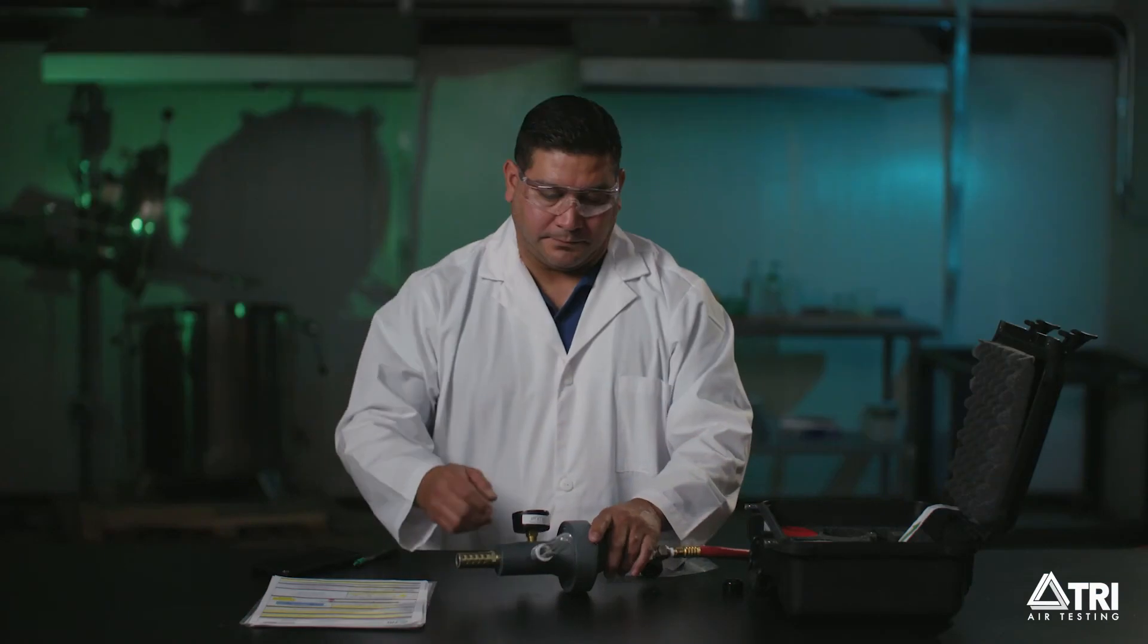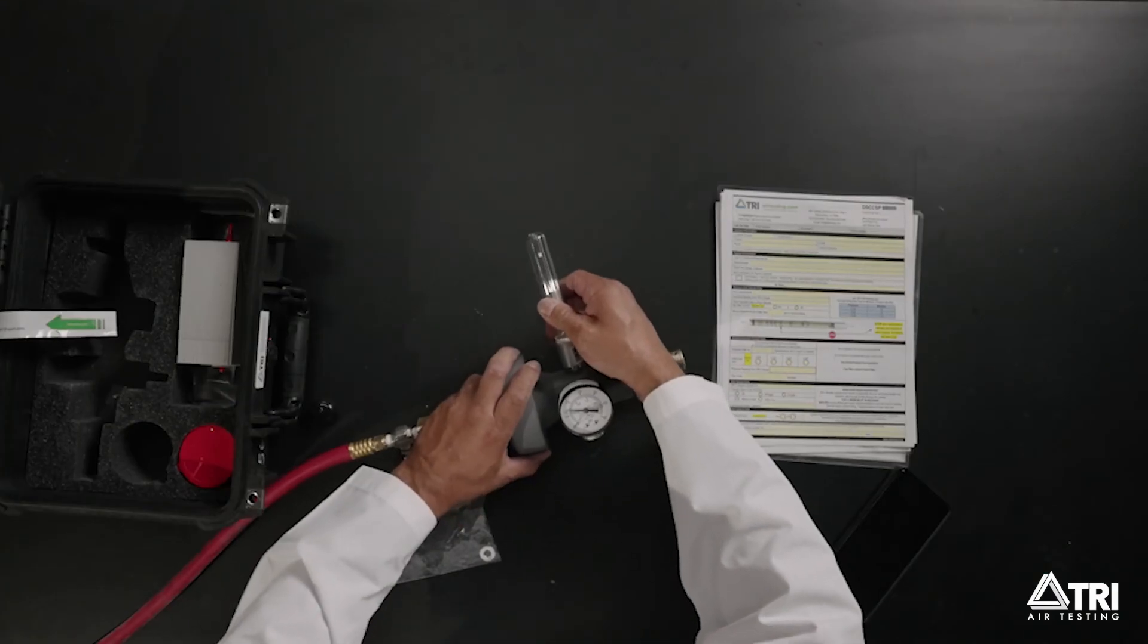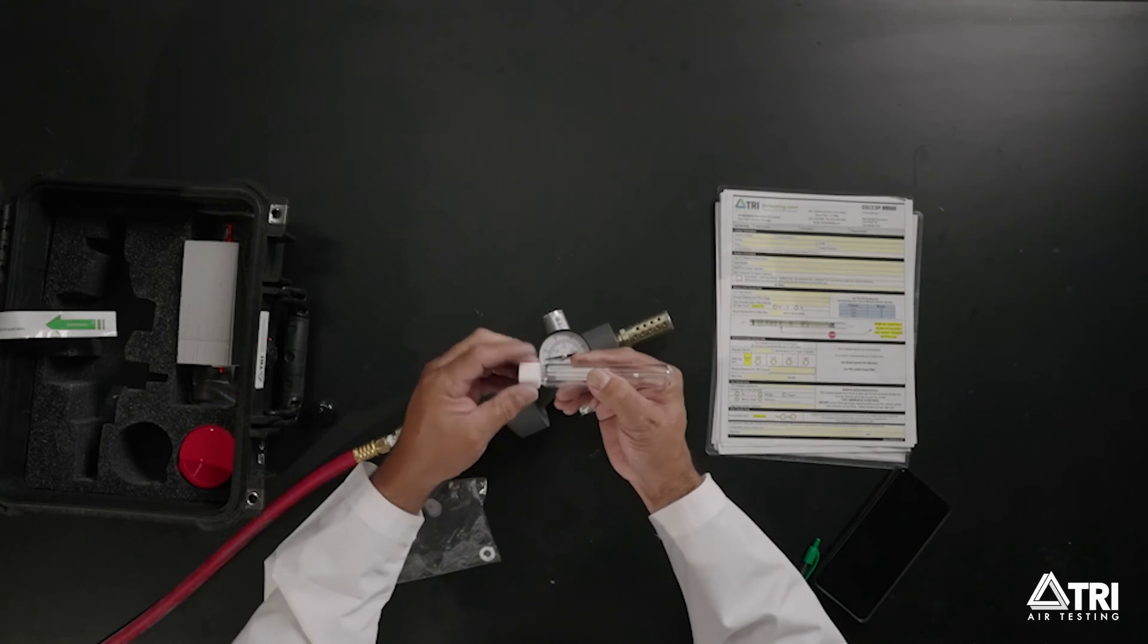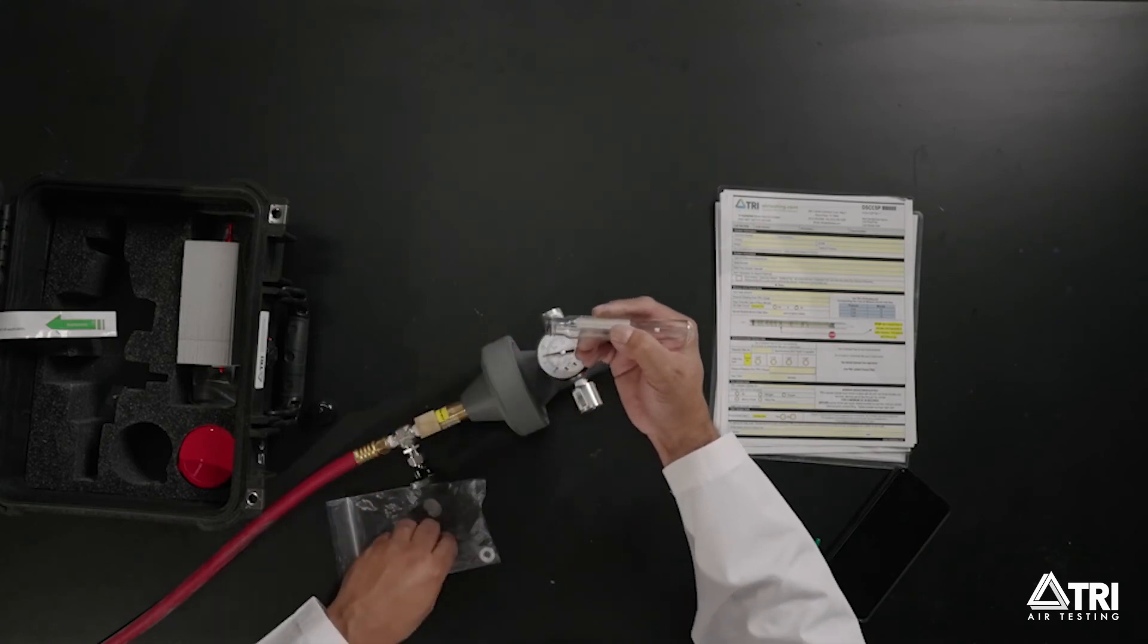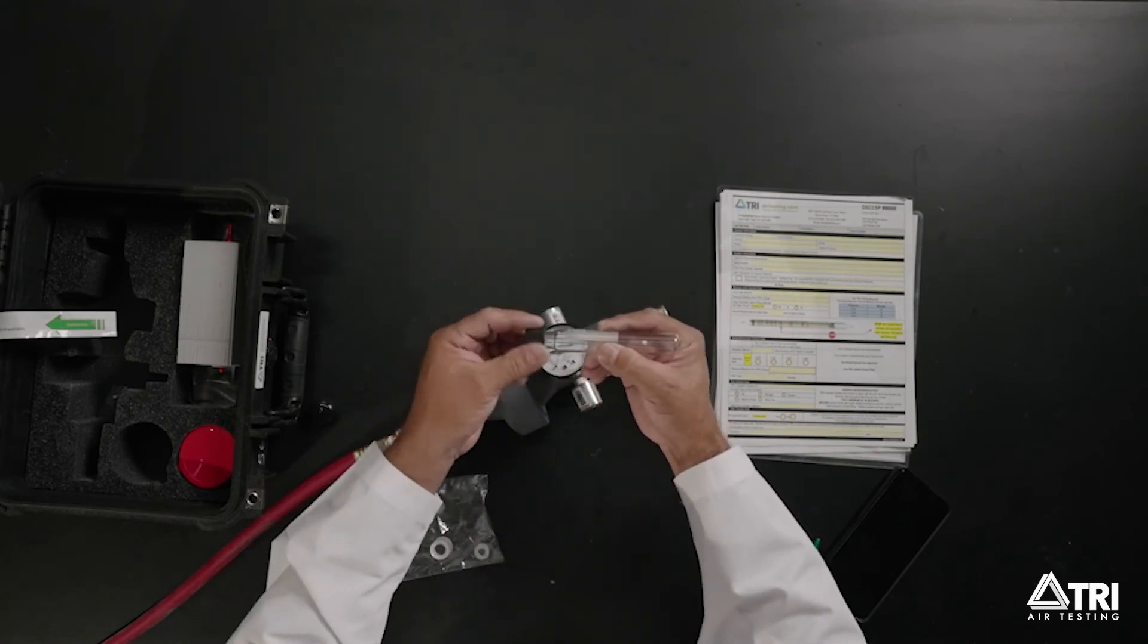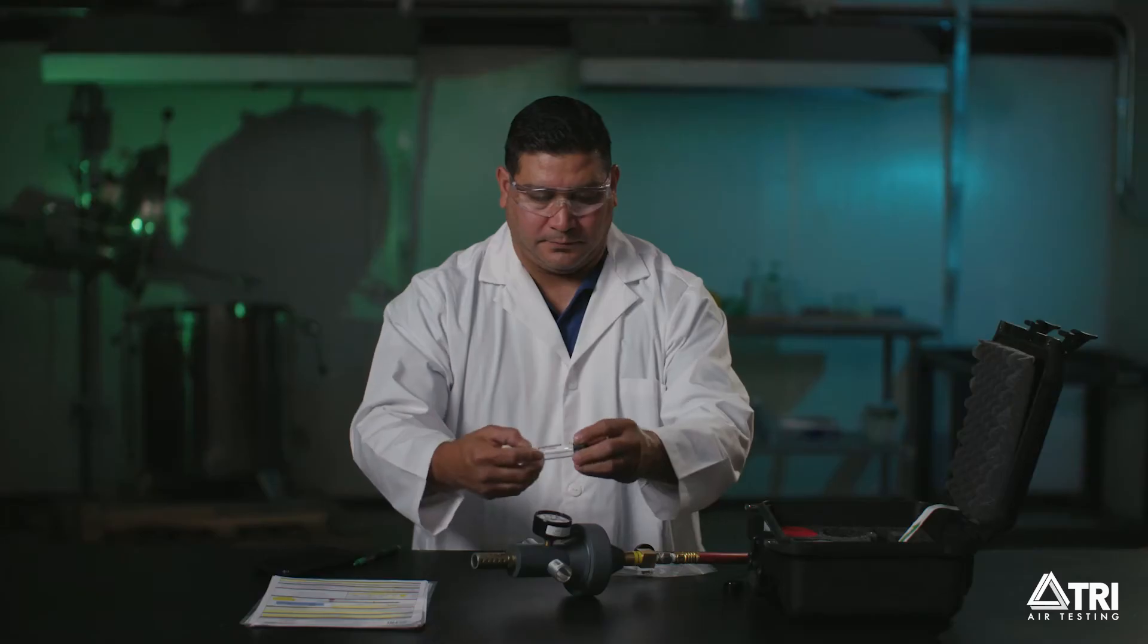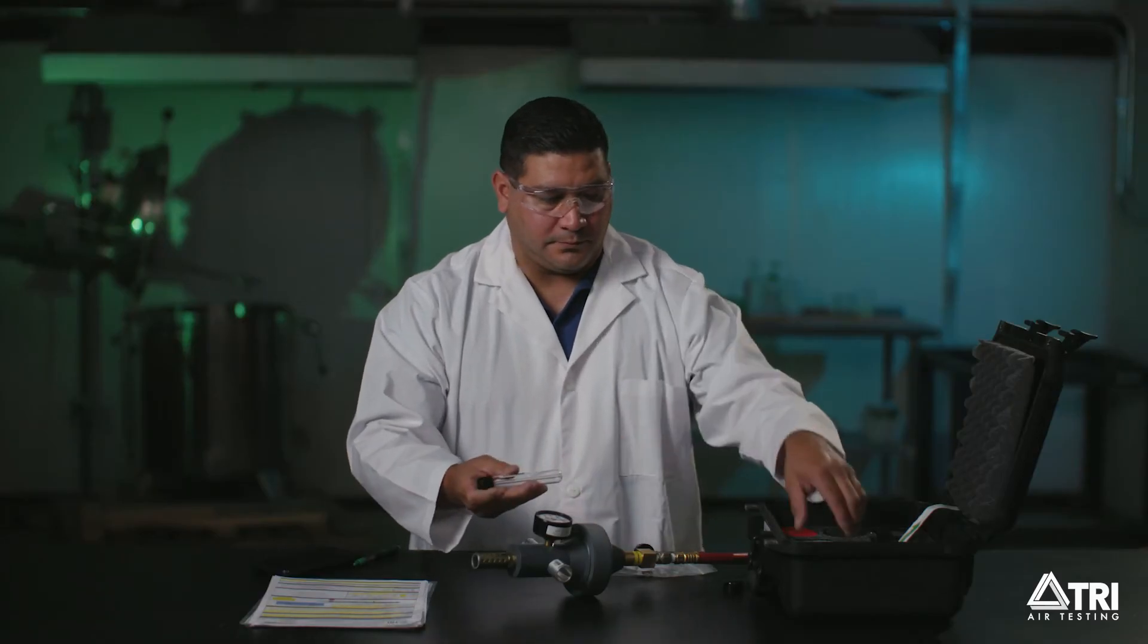While the gas is still flowing, remove the sample bottle. Remember, do not twist and replace the white sampling cap with the black shipping cap. The sample must be returned with the black cap tightly in place or the sample will not be analyzed.